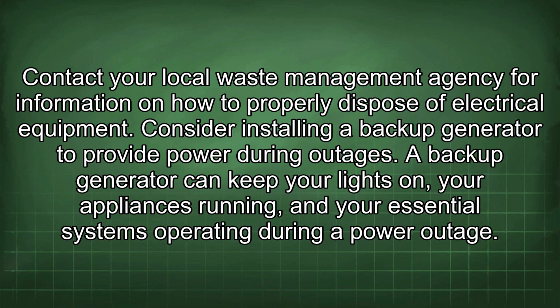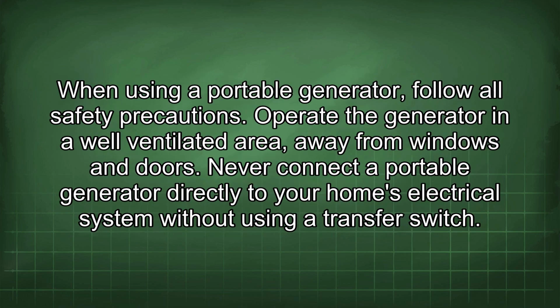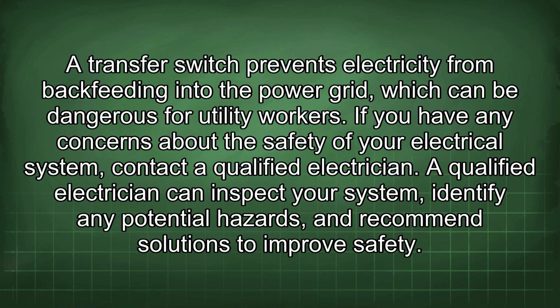Consider installing a backup generator to provide power during outages. A backup generator can keep your lights on, your appliances running, and your essential systems operating during a power outage. When using a portable generator, follow all safety precautions. Operate the generator in a well-ventilated area, away from windows and doors. Never connect a portable generator directly to your home's electrical system without using a transfer switch. A transfer switch prevents electricity from backfeeding into the power grid, which can be dangerous for utility workers.